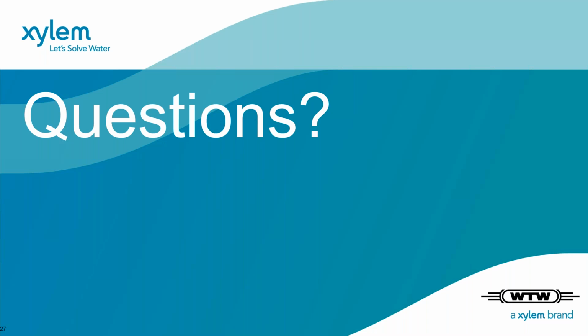Okay, thank you. Is there a way to prevent phosphate analyzer sample membranes from being fouled or clogged by algae? That filter membrane doesn't have an automatic cleaning, but thanks to the big surface, we have long maintenance intervals for that filter, dependent on the application. As I said, you can easily take it out and clean it manually, but there is no automatic cleaning. Okay, and let's talk briefly about the life of the chemical bag.